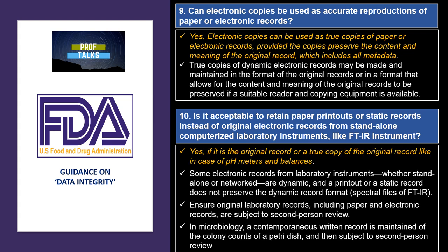Is it acceptable to retain paper printouts or static records instead of original electronic records for standalone equipment like FTIR? Yes, it is acceptable for instruments like pH meters and balances. However, some electronic instruments like FTIR are dynamic in nature, and a printout or static record does not preserve the dynamic record format. It should be ensured that original laboratory reports, including paper-based records, are subjected to a second-person review. In microbiology, a contemporaneous record is maintained of the colony counts of a petri dish and then subjected to second-person review.